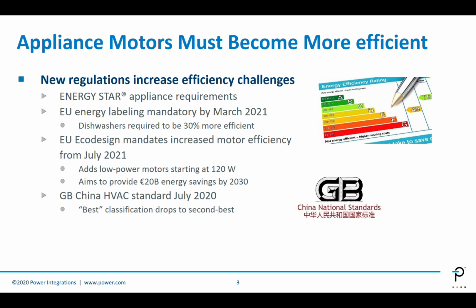Improved energy efficiency regulation is the main driver for change to brushless DC motors and advanced drive techniques like inverters. Let's go through some examples. Energy Star appliances save cost and energy. With the new eco-design energy regulation, the EU wants to save 20 billion euros in energy by 2030, which is an ambitious goal, only possible by making a couple of changes to the current standards. So they added low power motors starting from 120 watts. Before it was around 1 horsepower, and this opens the way for new applications to be more efficient.